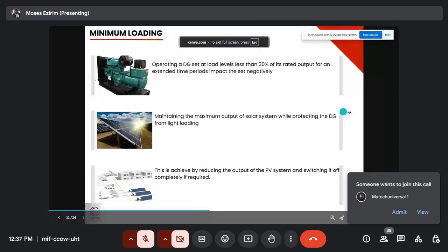All right. But the controller will ensure that the PV is not carrying all the load. Out of the 700, the PV will leave 240 for the generator. Do you understand? If the client load is below 240, what will happen? The controller will switch off the output of the PV completely and ensure that the generator is just carrying the load. All right. So that is what the minimum genset loading is all about.